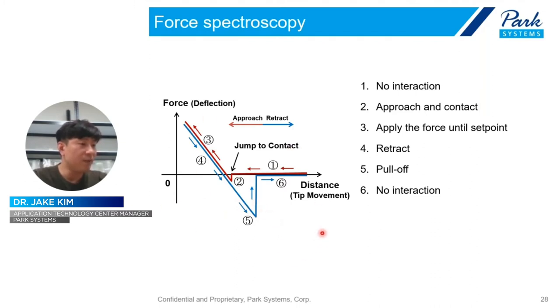This is one cycle of the FD curve. Start from number one, when the AFM tip and sample are quite far away, there is no interaction. But when the AFM tip gets close to the sample surface and makes contact, that is number two, and applies force until some specific value, we can call it the set point, like this, and reaches this value, then retracts, number four. At this point, number five, pull off, the AFM tip and sample detach. And number six is the return to the initial stage, no interaction. This is just one cycle of the force distance curve.